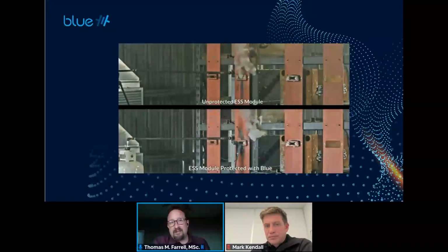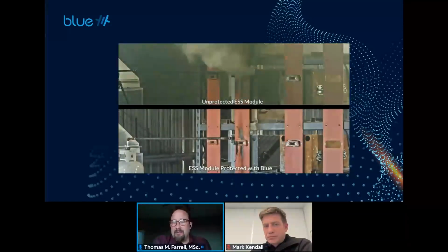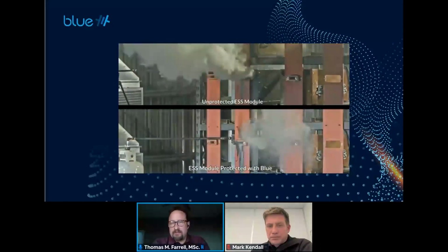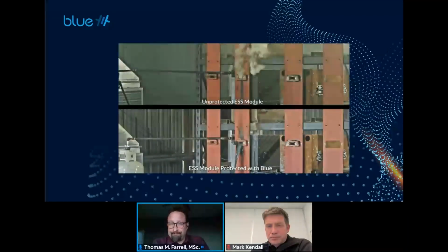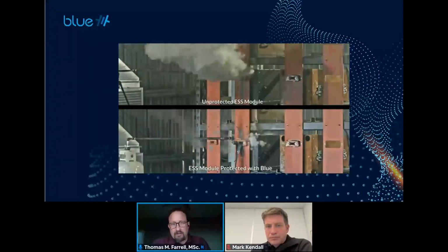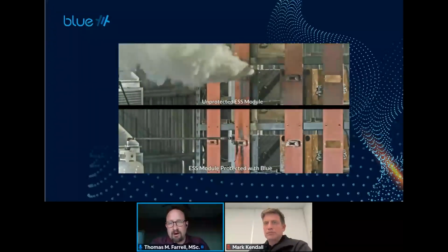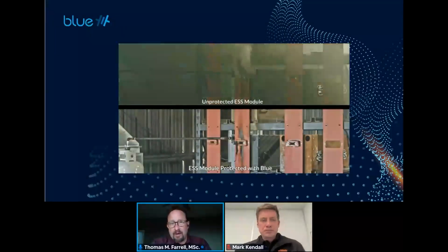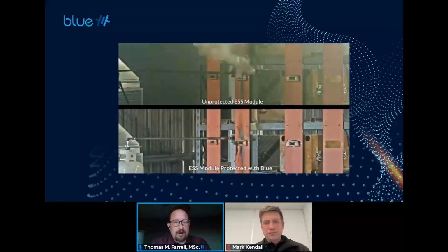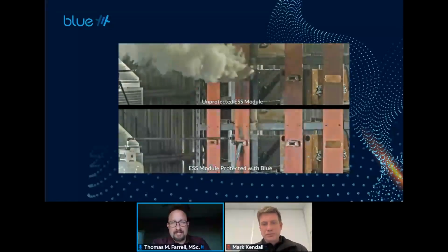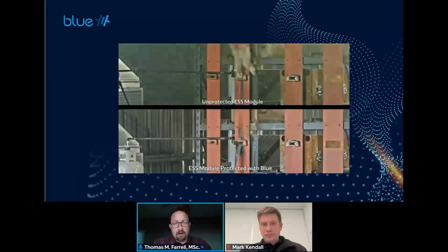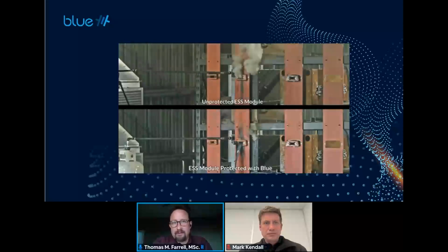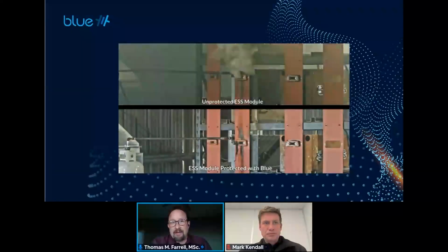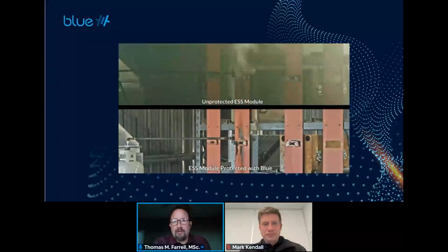What's also very interesting in this case with blue, the bottom video, is you do see runoff. In this test we used about 26 gallons of blue, and most of it remains in the module. Some of it does run off as part of our safety factor, but at the end of the thermal runaway, you're looking at just a few gallons of blue on the ground to clean up, which can be contained effectively using berms around your ESS, or by having good seals at the bottom, or a pan below your rack.